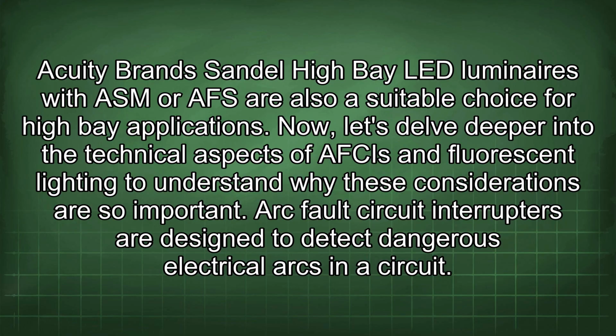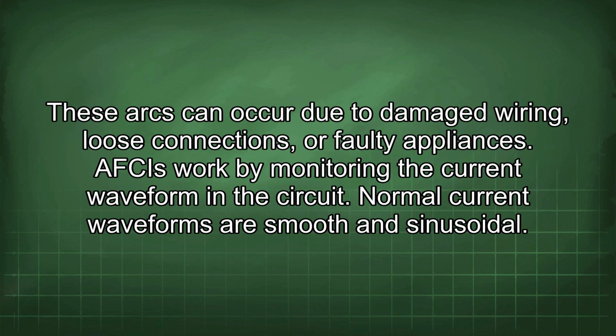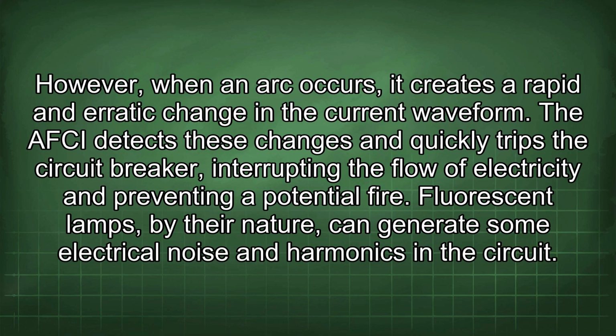Now let's delve deeper into the technical aspects of AFCIs and fluorescent lighting to understand why these considerations are so important. Arc fault circuit interrupters are designed to detect dangerous electrical arcs in a circuit. These arcs can occur due to damaged wiring, loose connections, or faulty appliances. AFCIs work by monitoring the current waveform in the circuit. Normal current waveforms are smooth and sinusoidal. However, when an arc occurs, it creates a rapid and erratic change in the current waveform. The AFCI detects these changes and quickly trips the circuit breaker, interrupting the flow of electricity and preventing a potential fire.